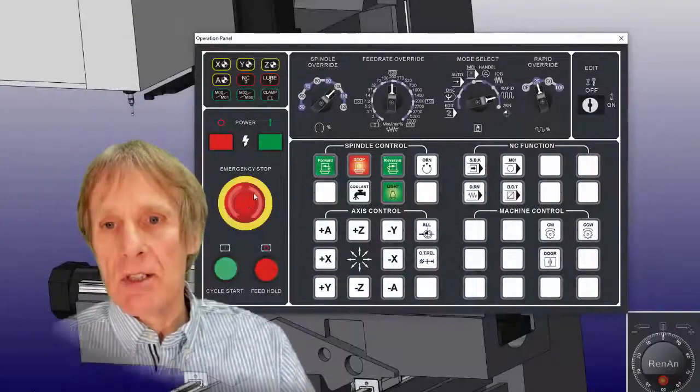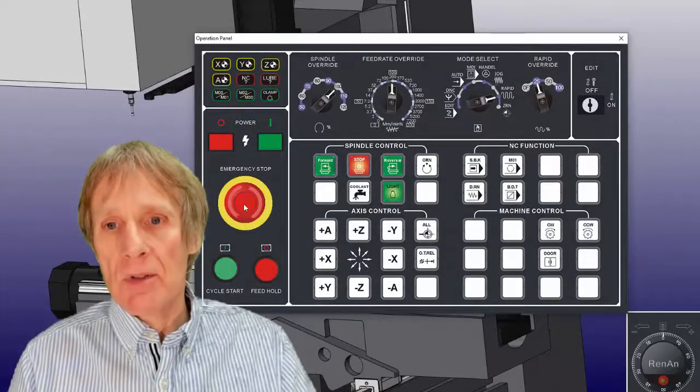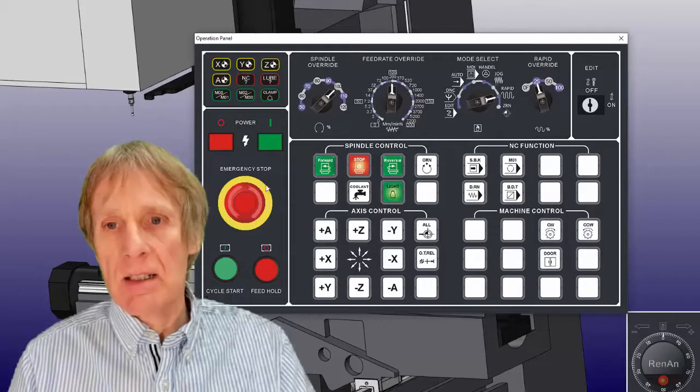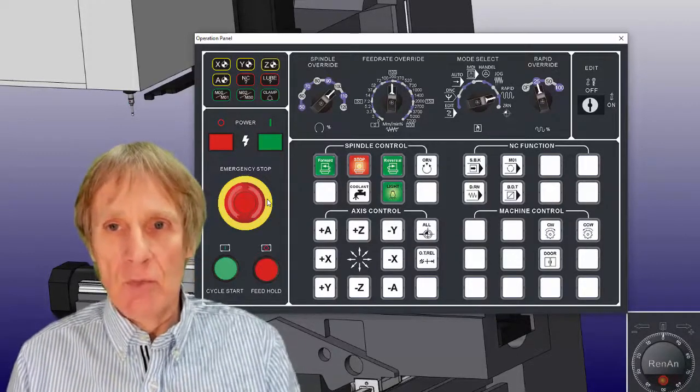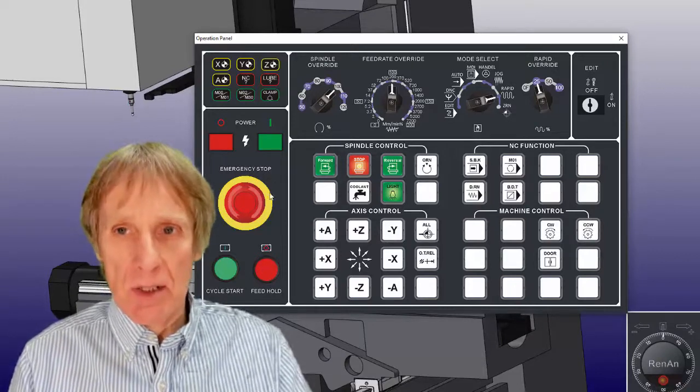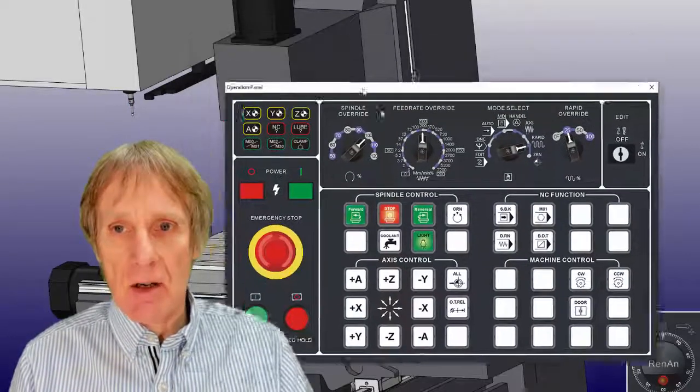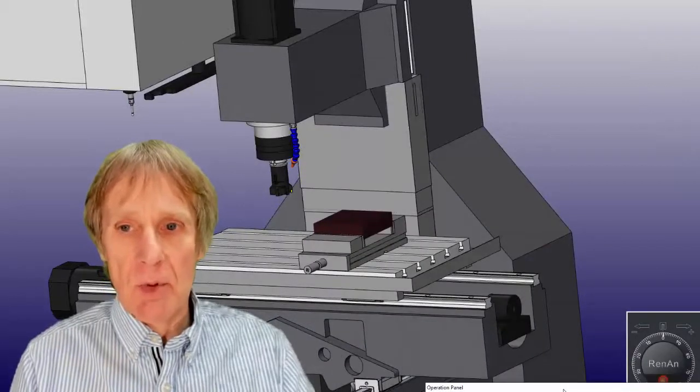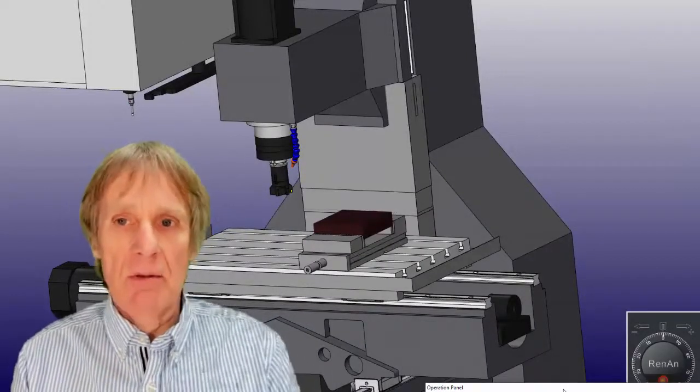When we come to turn the machine back on, the first thing we do is clear the emergency stop. You'd have to rotate that emergency stop button, and that releases it. Then you would hit the reset button. Now what we have to do when we first turn a machine on is pass it over what we call a reference point, and we call this zero return.